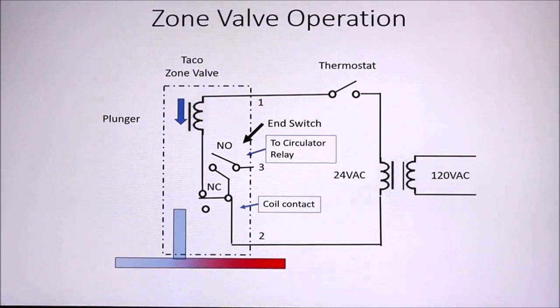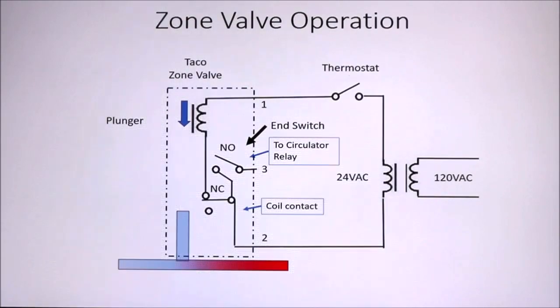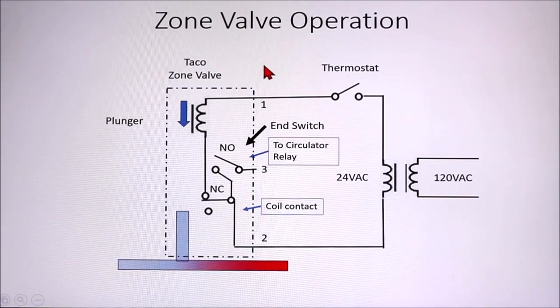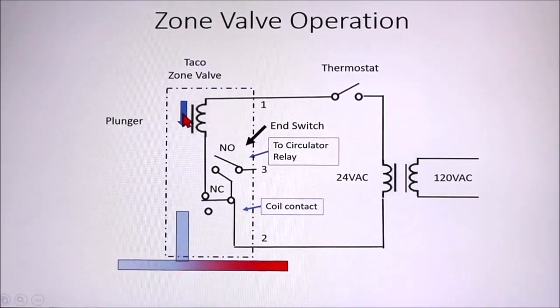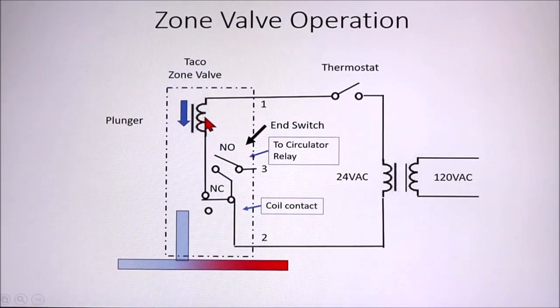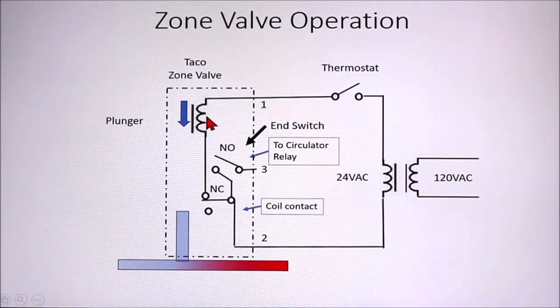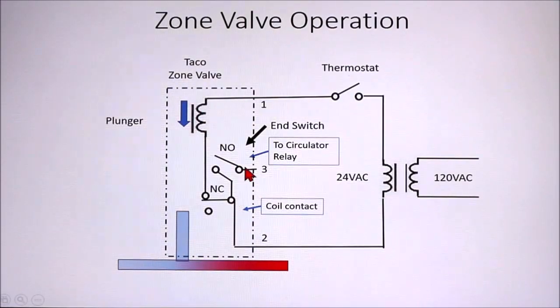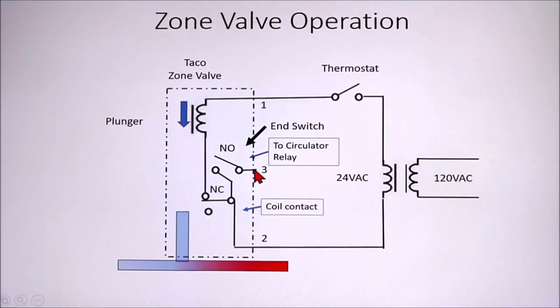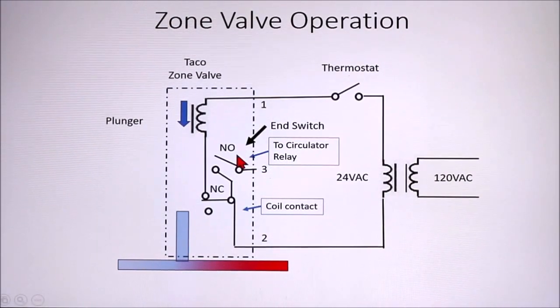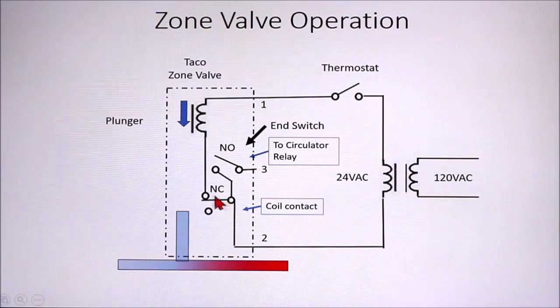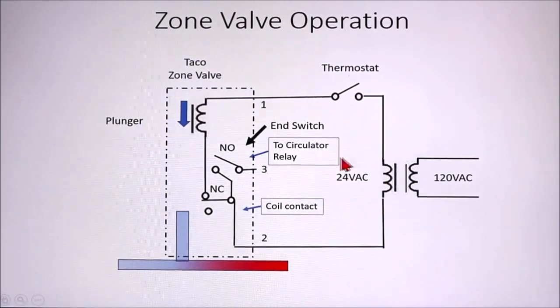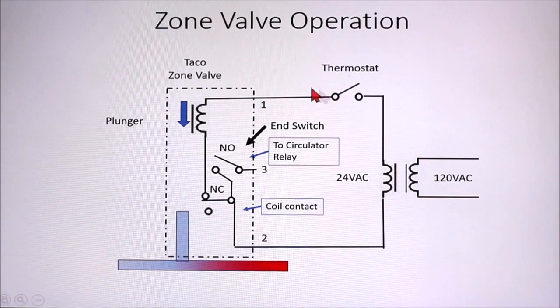Okay, this is a diagram of a zone valve and how it operates. In this diagram we have a thermostat right here that calls for heat. We have the Taco zone valve that I showed you earlier, which has a plunger and a coil. A coil heats up a mass of wax and grease that pushes the plunger when it gets hot. It has two contacts. This contact goes to the circulator relay. It's sometimes called an end switch. And then there's a coil contact which allows current to flow through the coil, and we'll see how this works in a minute. There's also a 24-volt AC transformer here, which powers the zone valve.